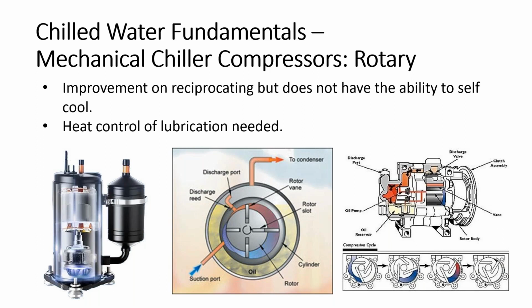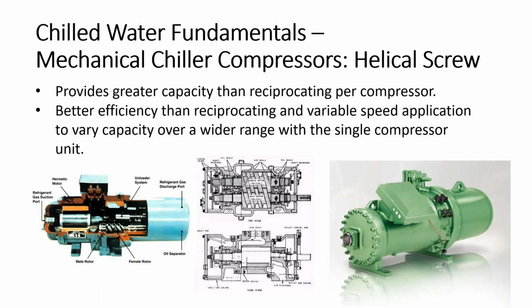These were handy for small applications, but they also upgraded to large chillers and actually applied them there, where they could actually use them in chillers to move a lot of refrigerant, but they also had to manage that lubrication control. They had to cool that at the same time. So these are very effective though, because they are more efficient than the reciprocating, but you still have to manage them a lot better.